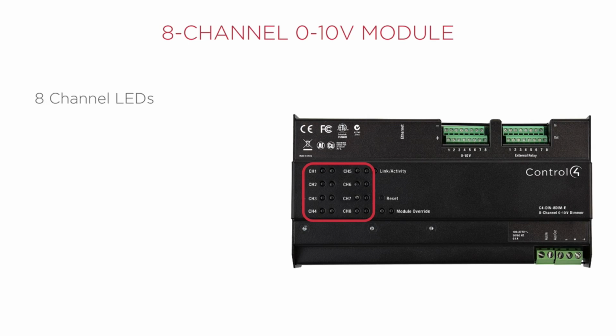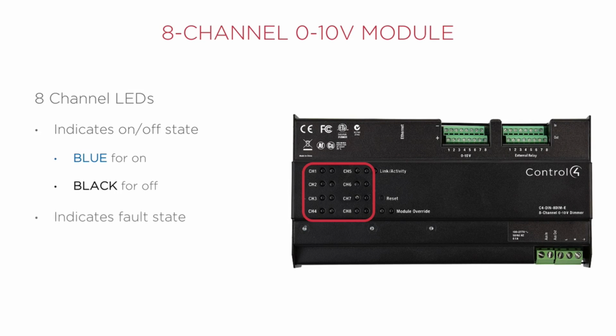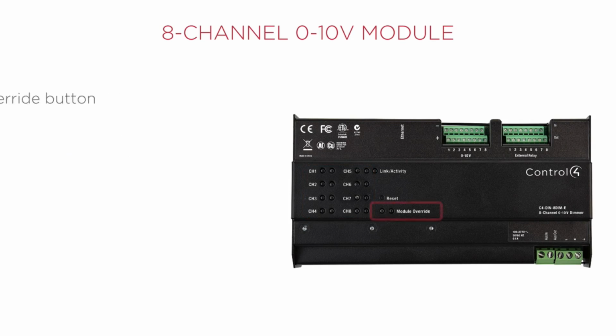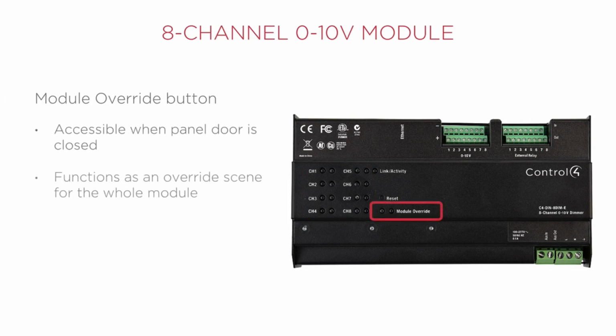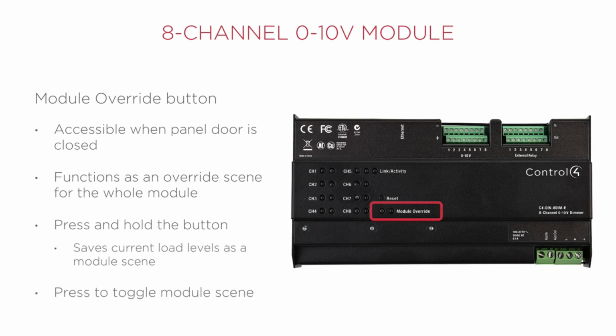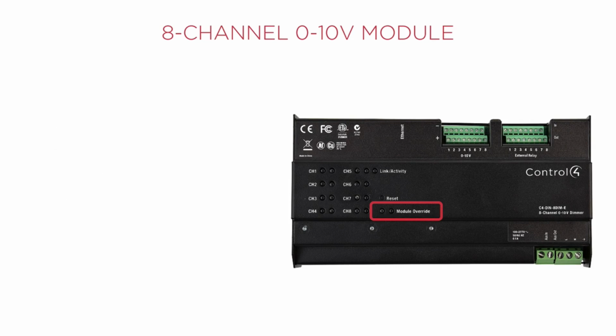The channel LEDs indicate the on or off state, blue for on, black for off, or to indicate a fault state. If it lights up red, there is a short circuit on that channel. The module override button is accessible when the panel door is closed and functions as an override scene for the whole module. Once the loads are set to their desired levels, press and hold the module override button to save the module scene. Pressing that button will toggle the module scene.